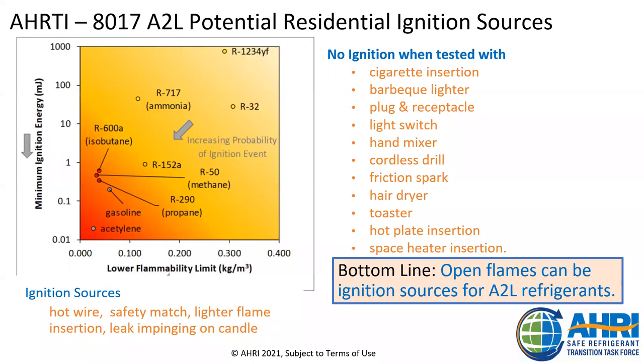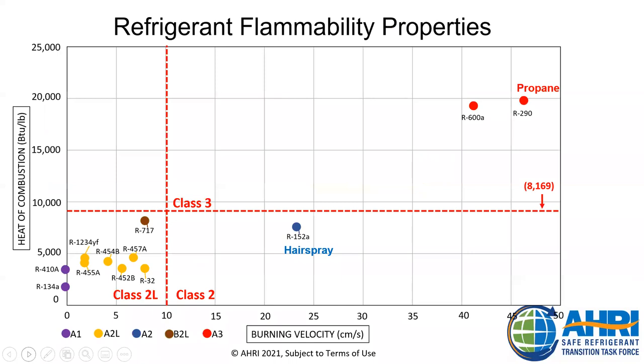Let's talk a little bit about A2L refrigerants, and I was mentioning earlier how difficult they are to ignite. So AHRI did a project, AHRTI 8017, where we looked at a lot of ignition sources in a residence, and we found with many, many ignition sources, there was no ignition when tested with these refrigerants. So a cigarette inserted into a concentration of refrigerant, a barbecue lighter, we looked at plugs and receptacles and shorts and a light switch and a hand mixer, cordless drills, space heaters, and what we found was, bottom line, open flames were really one of the only ignition sources that were viable or able to ignite the A2L refrigerants. We also found potentially a very hot wire, but again, kind of hard to conceive that in certain areas, but these are the ignition sources we found. And again, very interesting that we didn't find a lot of things that could ignite A2L refrigerants.